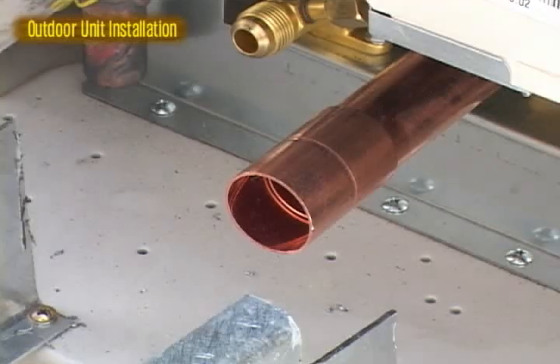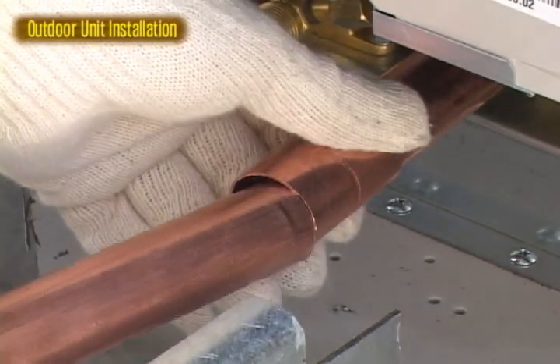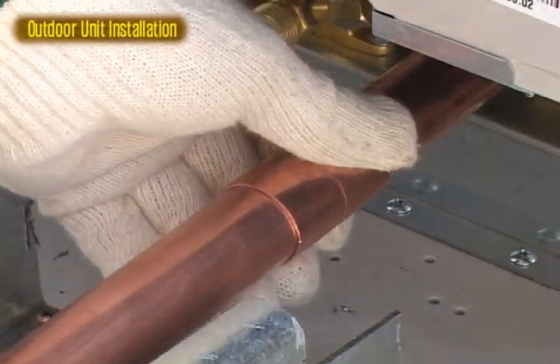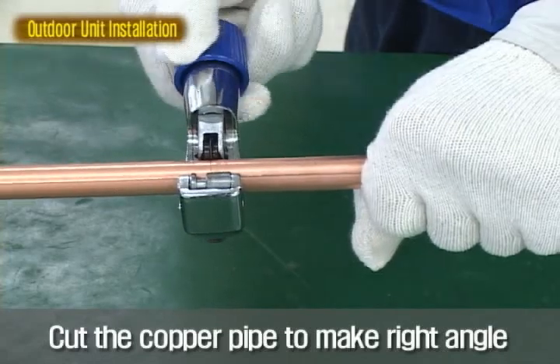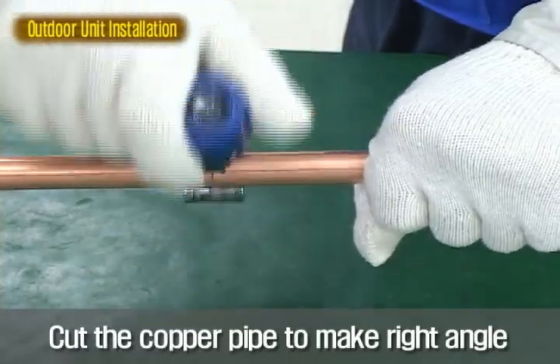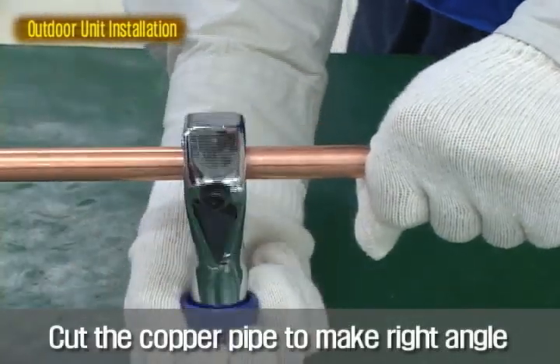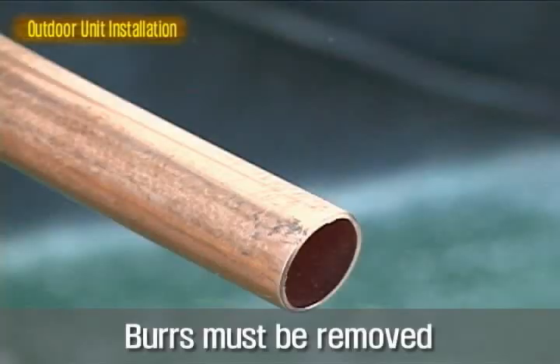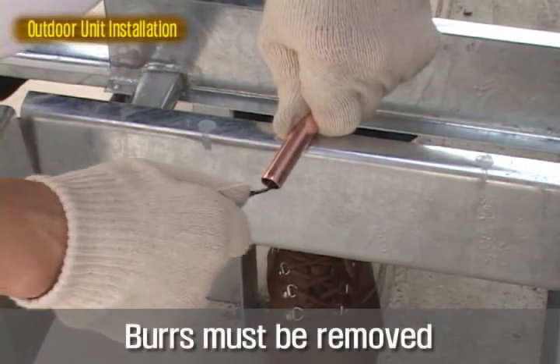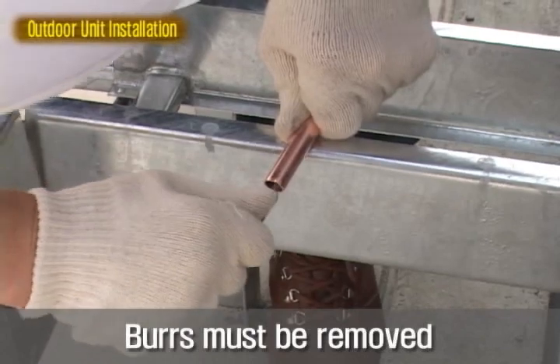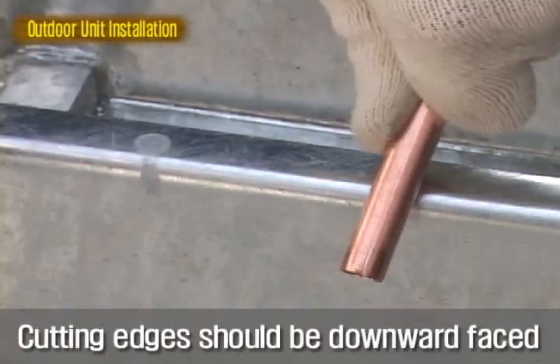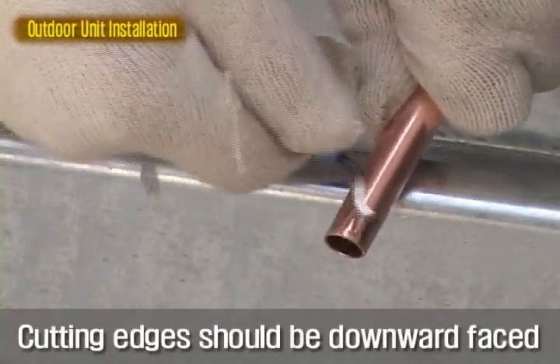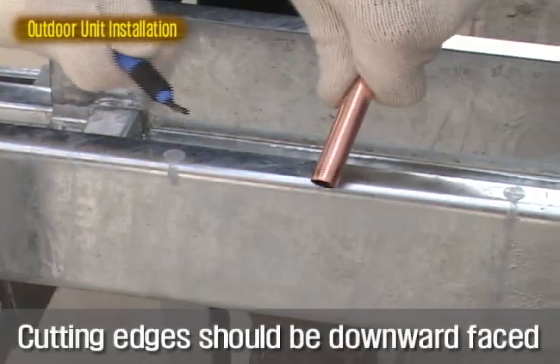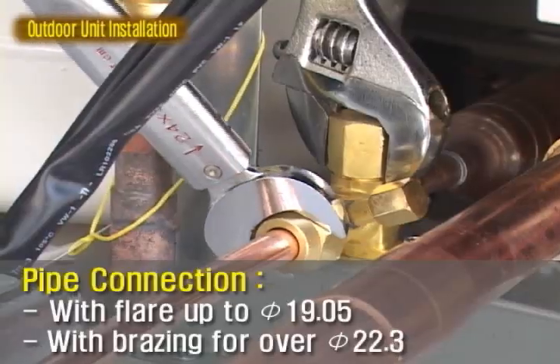Cut and connect the copper pipe by the measured length to the service valve. To cut the copper pipe, rotate the cutter 2 turns clockwise and then tighten it once slowly so as not to make deformation. After cutting, burrs must be removed with a scraper, otherwise it will cause leakage. The pipe end is to be downward so as to prevent burrs and chips from entering the pipe.